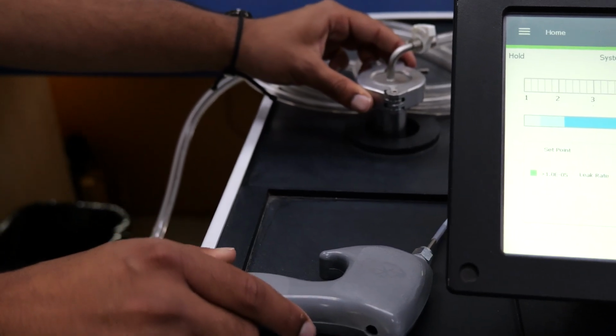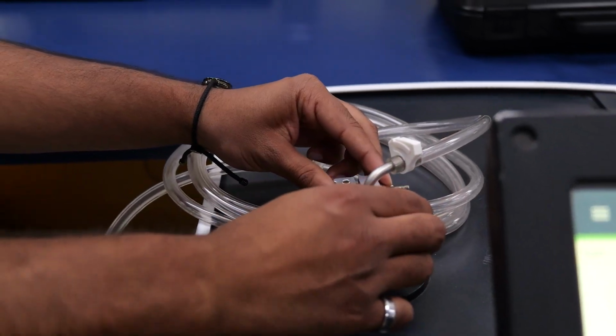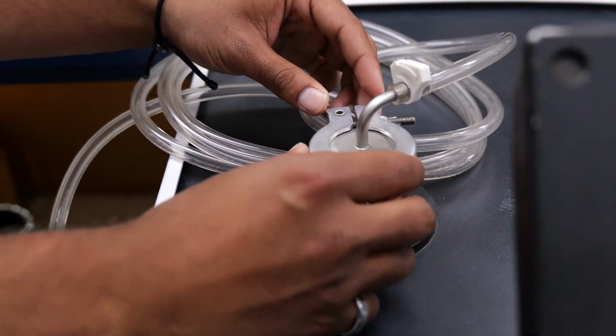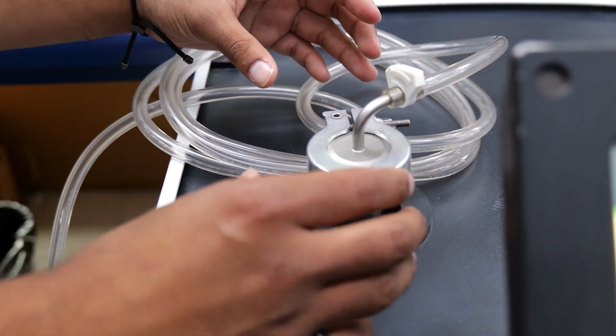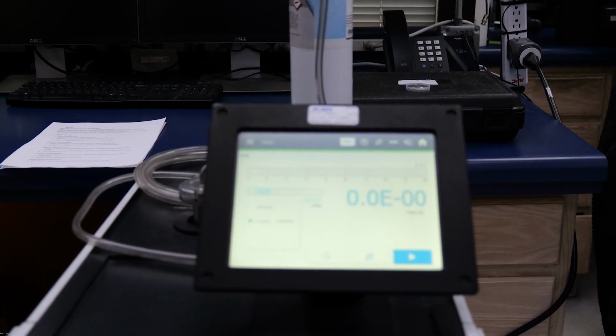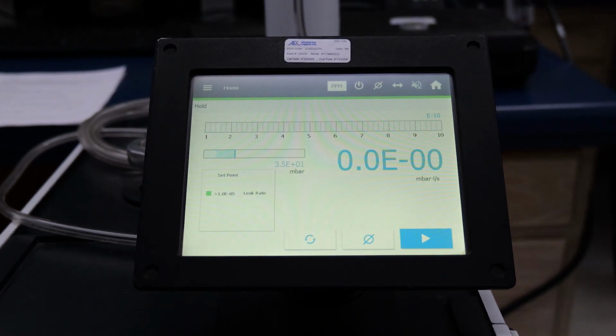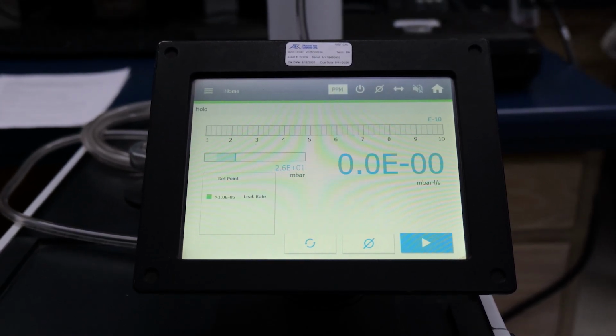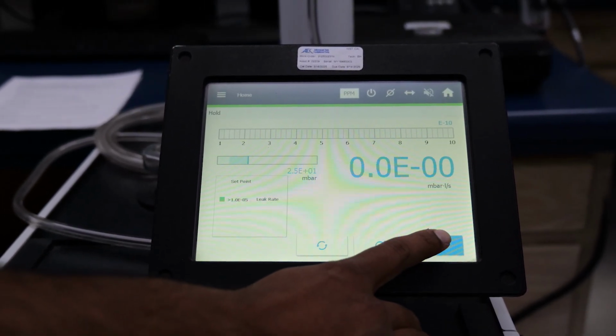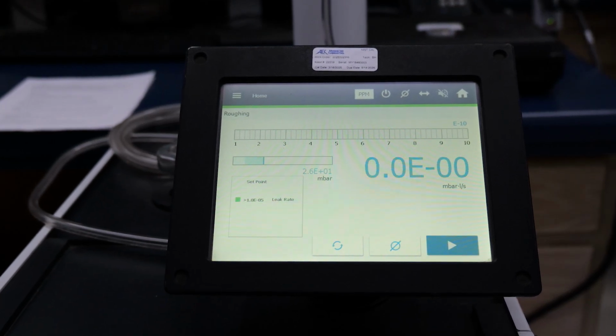Looking at our helium leak detector, you can see that we have our sniffer probe connected to the inlet port of the leak detector, with a hose clamp wrapped around it to ensure we don't have any air leaks. After allowing the helium leak detector to warm up for about 30 minutes, you should reach a point where the system is ready to test. You can go ahead here and press the play button to start the test.